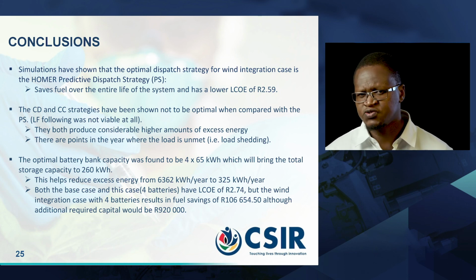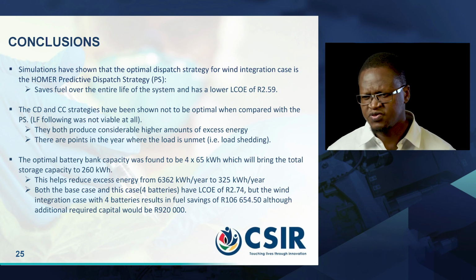This helps to reduce the excess energy from 6,362 kilowatt hours per annum to 325 kilowatt hours per annum. But it also has the disadvantage of an additional capital cost of 920,000 onto the system for the additional 2 batteries.